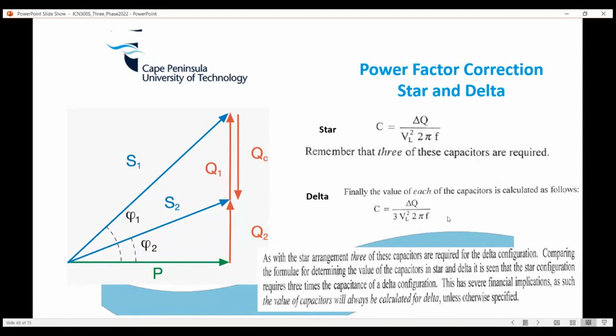So typically, when you're connecting capacitor banks, wherever it may be, it's typically connected in a delta configuration, because if you connect it in star, obviously we have to pay more. So that's the idea. The equation which we'll be using a lot is essentially the one at the bottom here with the 3 VL squared 2 pi f, and I know it comes in your formula sheet.